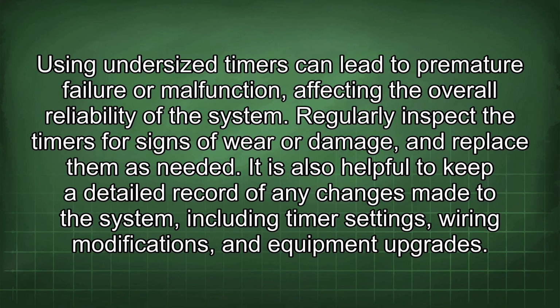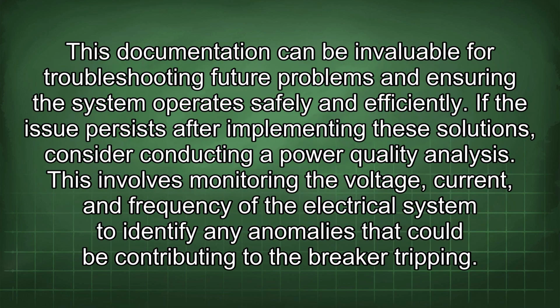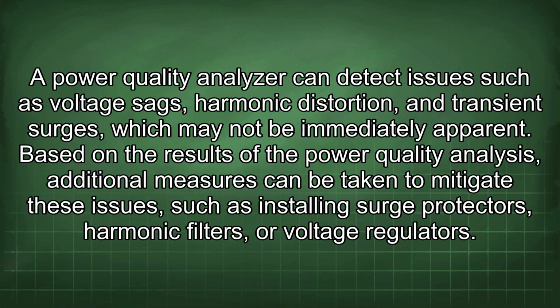It is also helpful to keep a detailed record of any changes made to the system, including timer settings, wiring modifications, and equipment upgrades. This documentation can be invaluable for troubleshooting future problems and ensuring the system operates safely and efficiently. If the issue persists after implementing these solutions, consider conducting a power quality analysis. This involves monitoring the voltage, current, and frequency of the electrical system to identify any anomalies that could be contributing to the breaker tripping. A power quality analyzer can detect issues such as voltage sags, harmonic distortion, and transient surges, which may not be immediately apparent.